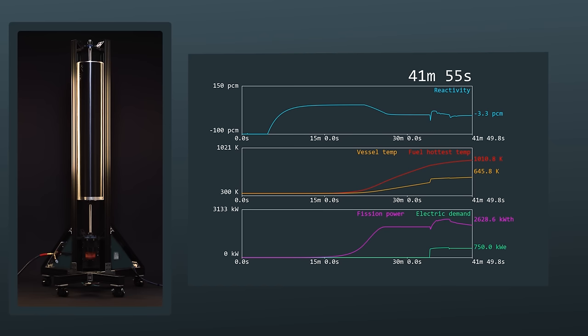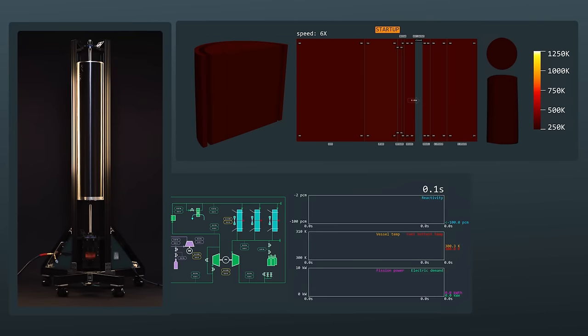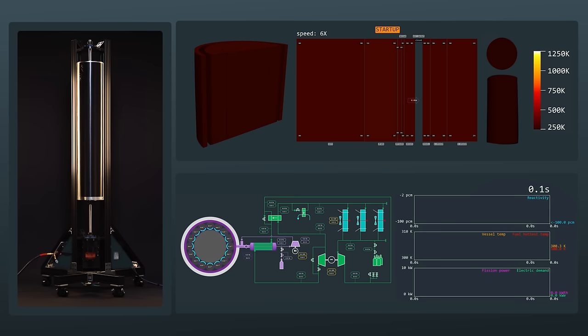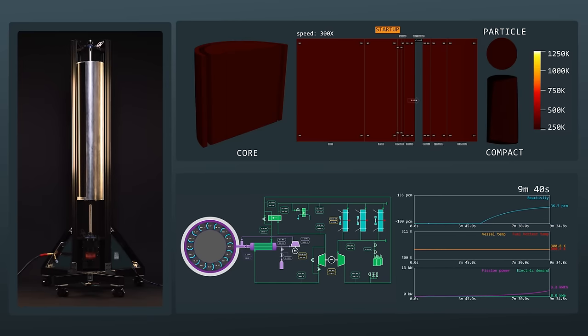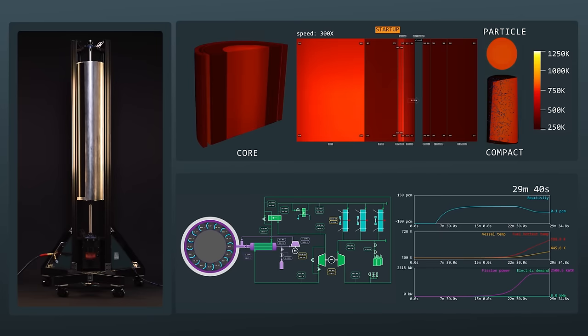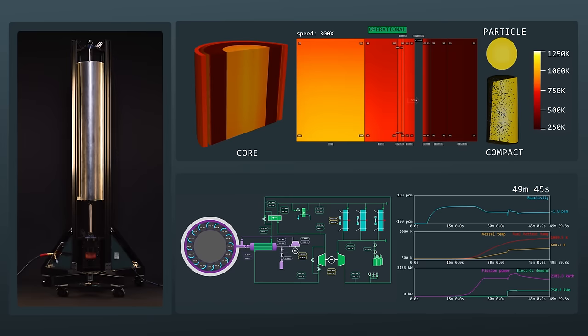SimEngine will now demonstrate integrated execution of the reactor digital twin with its real-time control system as it goes through a startup. Drums are rotated to insert reactivity until criticality is achieved. At this point, the neutron population starts growing exponentially. When the core starts to heat up due to the release of fission energy, the control system further turns the drums in order to maintain criticality. The drums move by an additional 30 degrees to offset the core's negative temperature feedback coefficient.